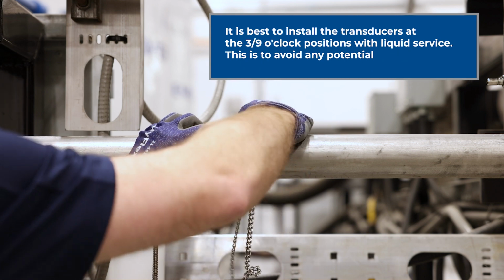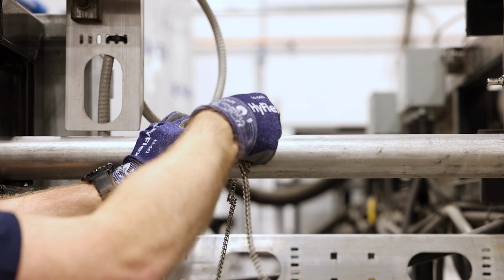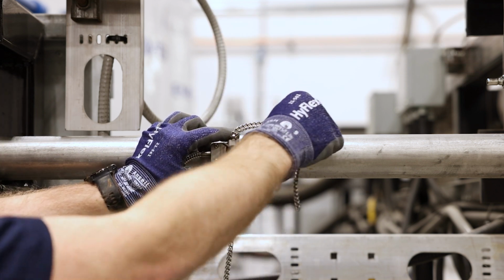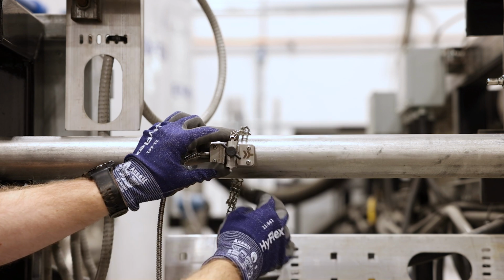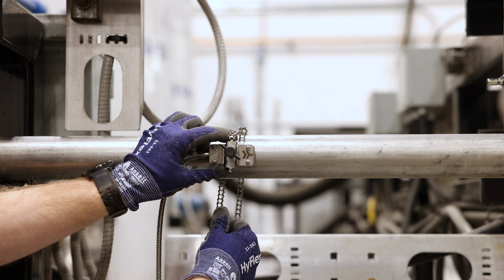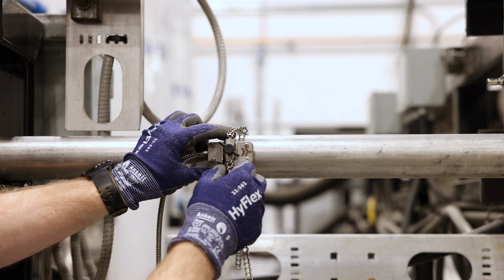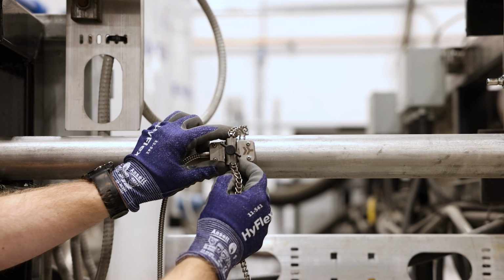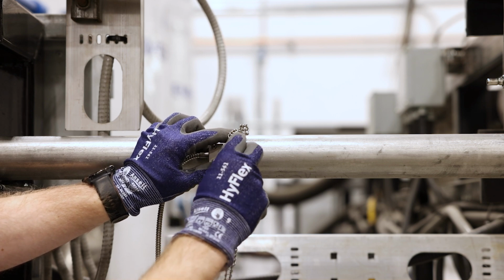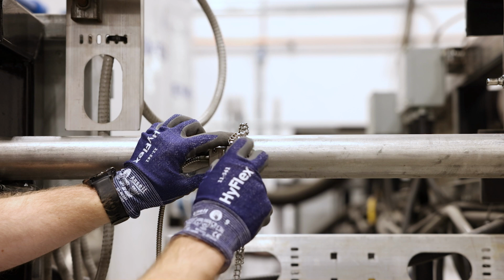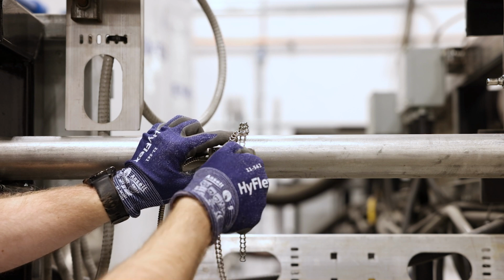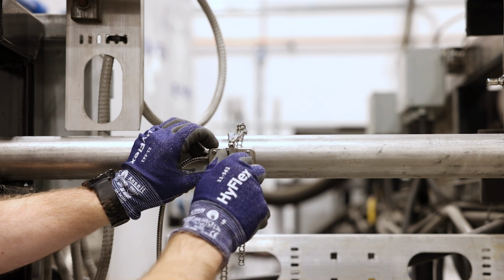Put our ladder chains over top of the pipe. It's easiest if you hook the top portion of the mount and then loop the bottom across. Once it's in the groove, you can tighten down the mount and ensure your transducers are horizontal for this particular installation.